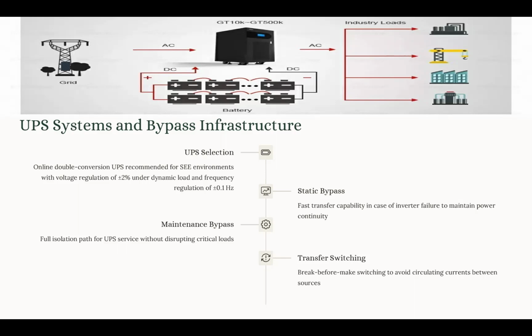Now, we also have bypass infrastructure, which allows continuous power to critical loads during UPS maintenance or UPS failures or overload of the UPS systems. We have a static bypass, which is an automatic fast transfer. When we say fast transfer, we mean less than 4 milliseconds. This is for when the UPS fails or is overloaded. It makes sure of uninterrupted power by transferring the load directly to the utility or the generator. Those static bypasses should be properly coordinated so we could avoid circulating current and voltage transients when we are transferring between the sources.